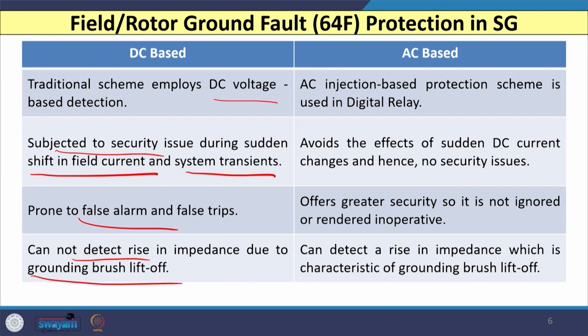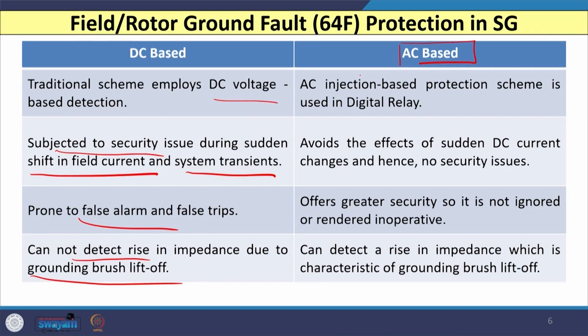The DC voltage-based detection scheme may fail to detect any increase in impedance due to grounding brush lift-off. Because of these disadvantages, most utilities now use AC voltage-based protection schemes, as used in most digital relays. This scheme avoids the effect of sudden changes in DC current, offers greater security during system transients, and can detect increase in impedance particularly in case of grounding brush lift-off.